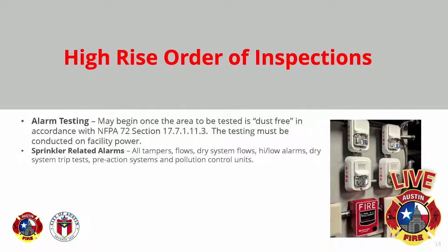We normally start off with sprinkler-related alarms. That's tampers, flows, dry systems, high-low alarms, dry system trip tests, pre-action systems, and pollution control units. A typical 35-story high-rise office shell, you're probably looking at 2 days alone just testing sprinkler-related equipment.